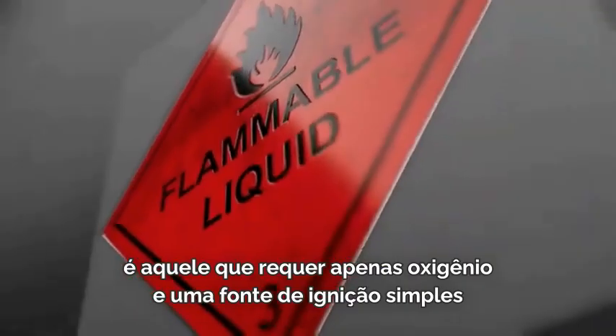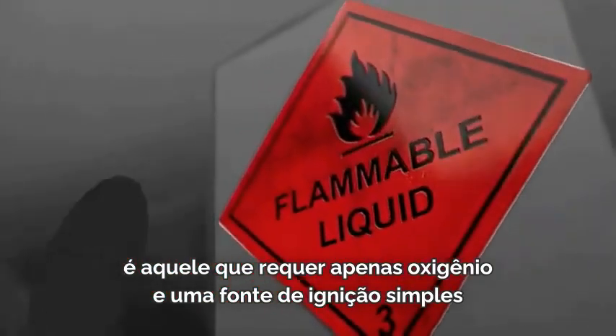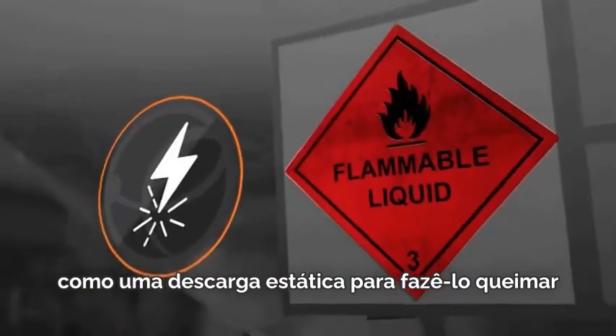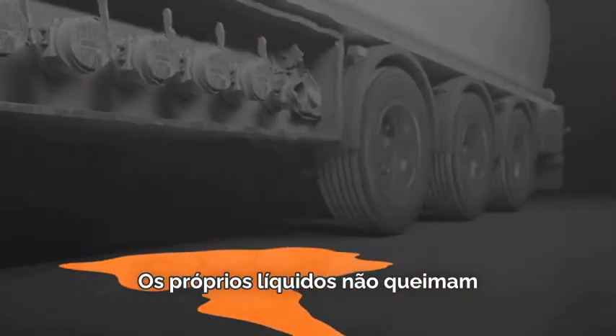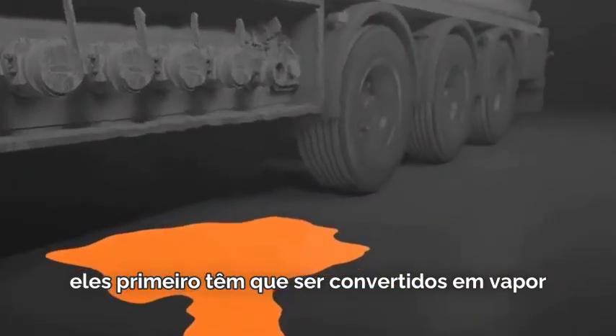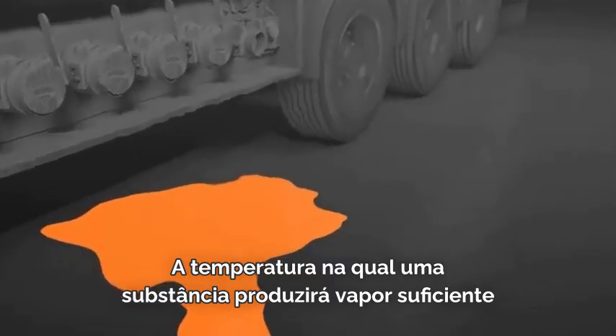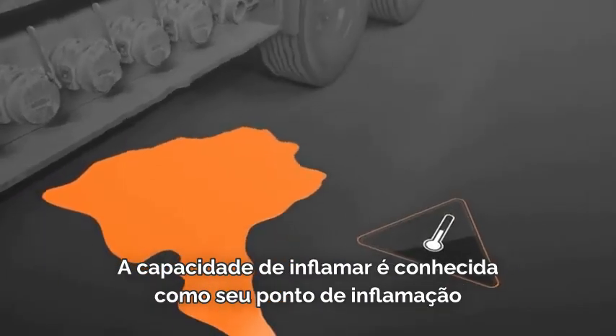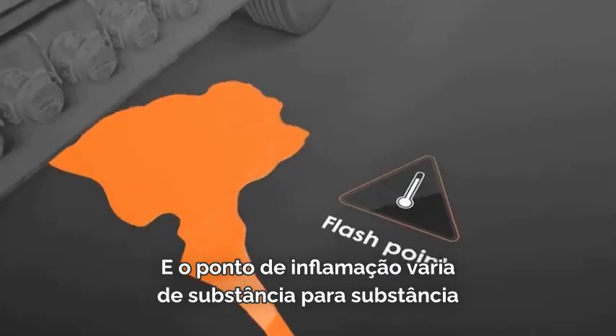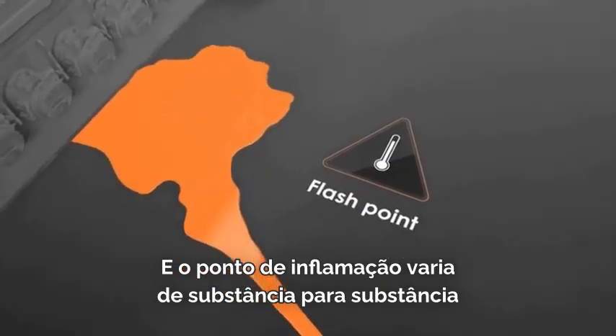A flammable material, usually a liquid or a gas, is one which only requires oxygen and a simple ignition source, like a static discharge, to make it burn. Liquids themselves don't burn. They first have to be converted to a vapor. The temperature at which a substance will produce enough vapor for it to ignite is known as its flash point, and the flash point varies from substance to substance.